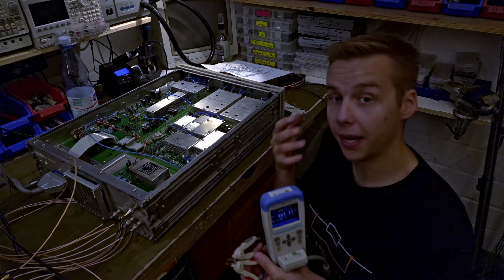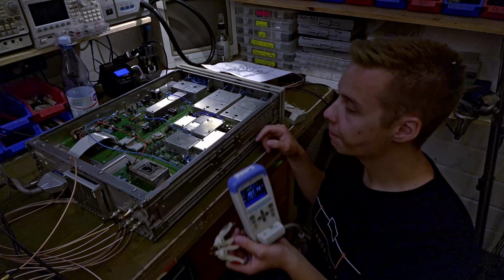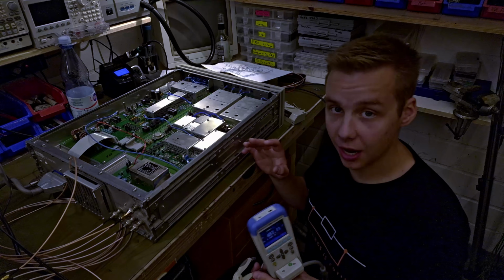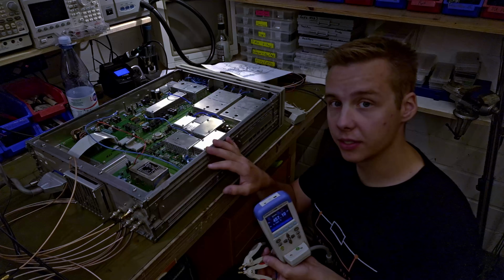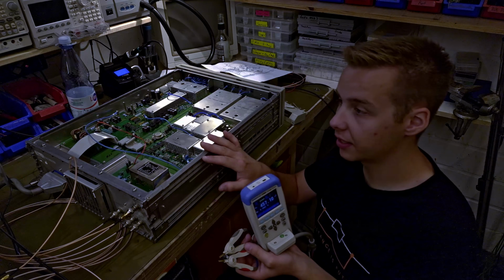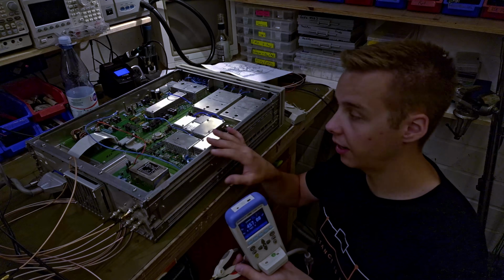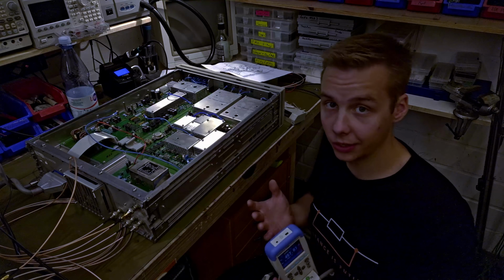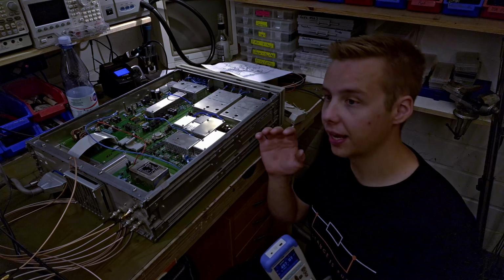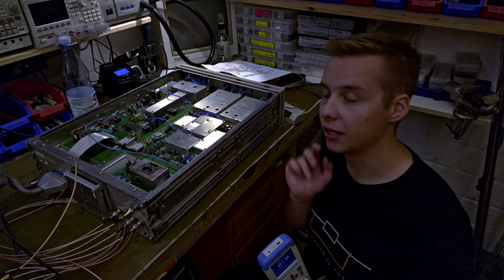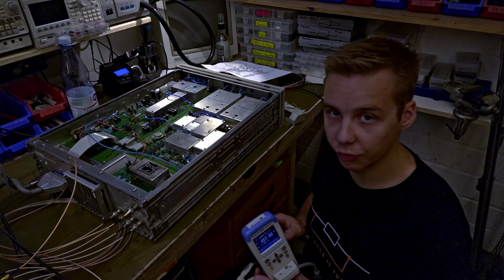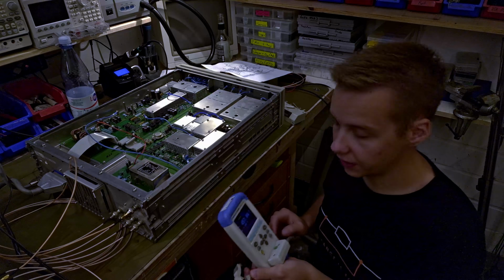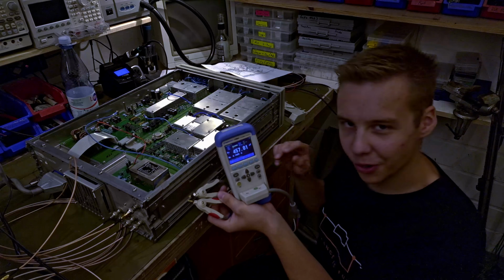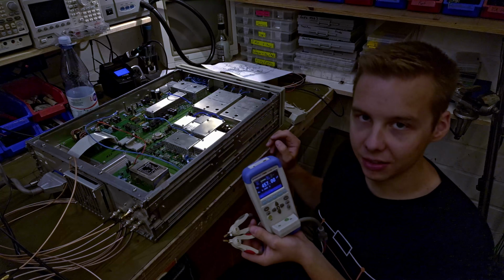So for example, you can apply a DC bias to the thing. Again, the frequency range is larger, and also you can do frequency sweeps. This thing cannot just test at a set of fixed frequencies. You can actually have it sweep all the way from 100 Hz to 40 MHz and actually see the change in the impedance over frequency. Again, this thing cannot do that either. Now, of course, this is a lot more convenient, but this thing can do more.